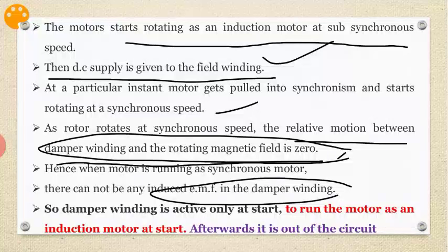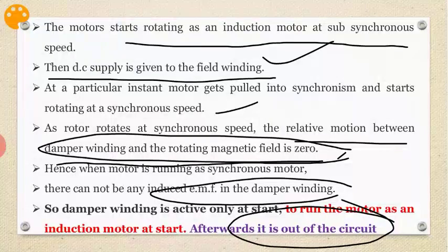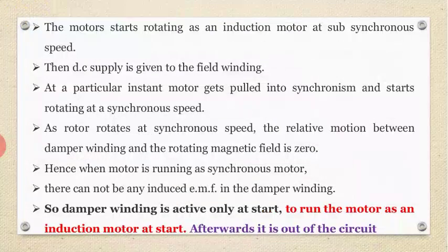Earlier it was there because it acts as an induction motor. Once it reaches synchronous speed, there is no EMF in the damper winding. So the damper winding is active only at start, to run the motor as an induction motor. Afterwards it is out of the circuit.